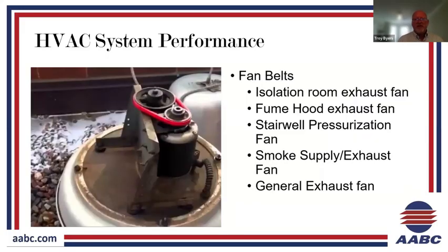So sort of staying with the fan belts and looking at some specific examples here. And you can add to the Q&A on this topic here. These are just some examples to throw out. When we look at isolation room exhaust fans, for instance, we've got indicators in that isolation room, room pressure monitors, right? That might indicate we're not maintaining proper pressure. That would sort of lead us to troubleshooting in this example, and maybe finding an issue with a fan belt. So in some areas we do have indicators. Another example would be a fume hood exhaust fan, and some fume hoods are equipped with low flow alarms that would indicate a persistent problem that might lead us to that.